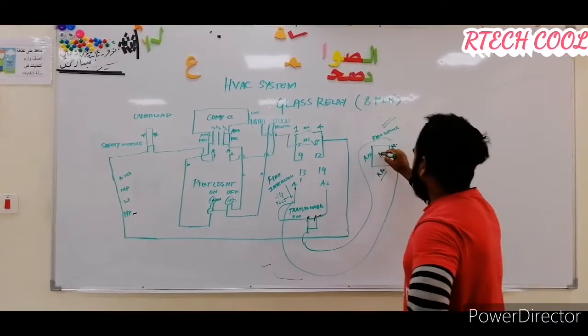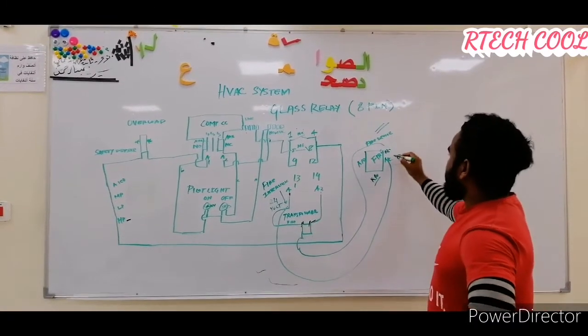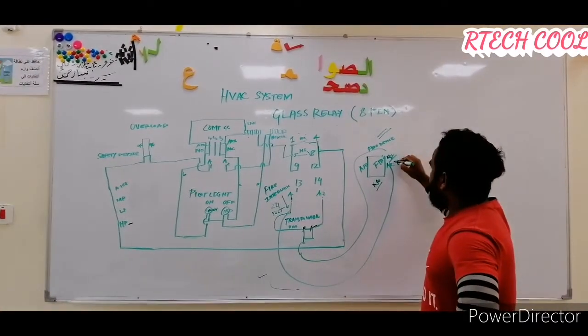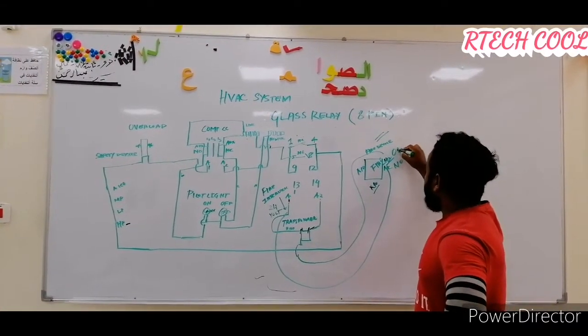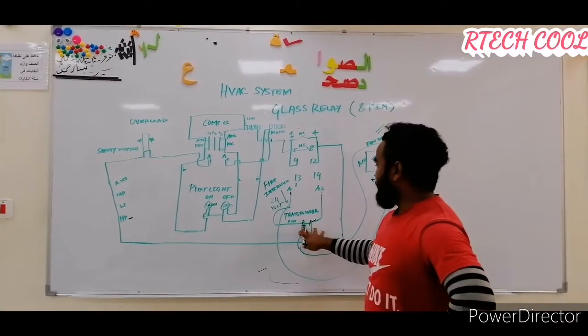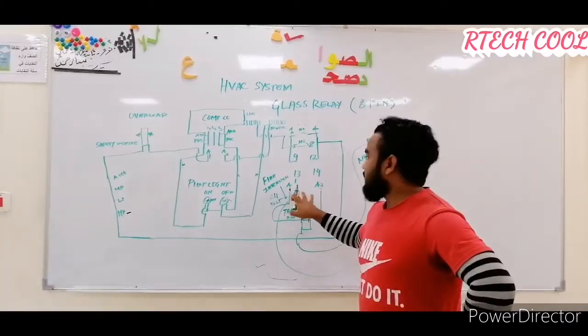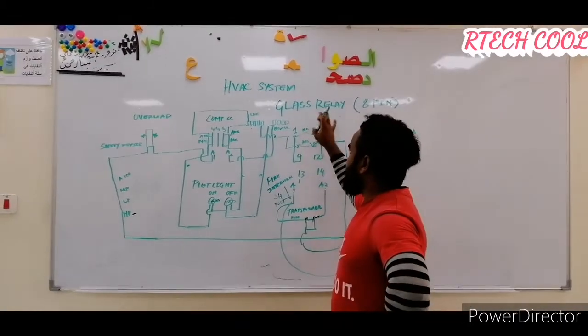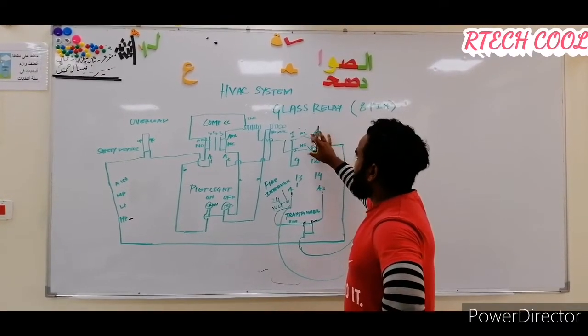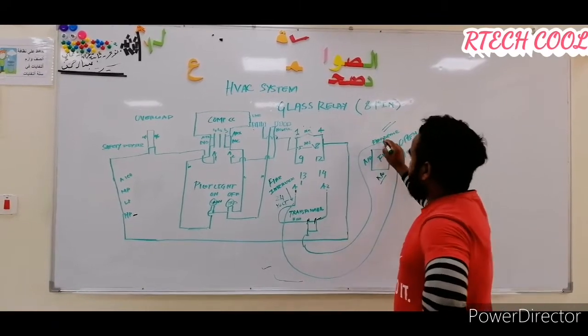If there is fire inside the building, the fire interlock NC contact will open. If that contact opens, the transformer will not supply 24V to our relay. If our relay does not energize, the NC stays NC and the NO stays NO — nothing changes. But if there is no fire, normally everything is fine, so it will change — the relay will energize.